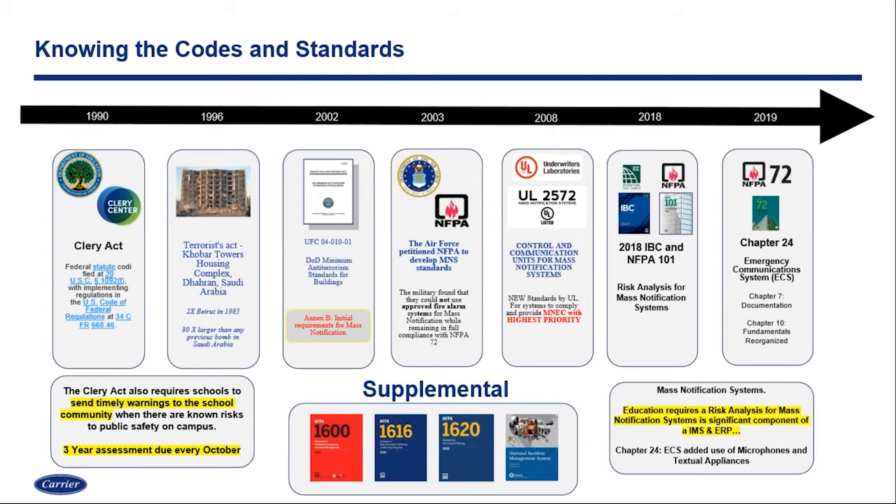With that come requirements for risk analysis — assessments over the last three years, due every October. From a code aspect, the Khobar Towers, the UFC, and really a combination of working with the Air Force and NFPA, we saw in 2003 more code language take place. From that, we saw NFPA change from the National Fire Alarm Code into the National Fire Alarm and Signaling Code, and Chapter 24 on emergency communications was added and continued to grow since then.